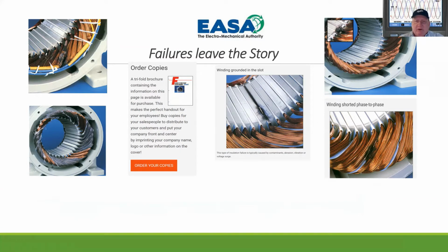So there's also a tool that's out there. Basically, the failures do leave a story. EASA has a product that shows what the motor stators look like when they fail, so you can determine the root cause of the motor failure. This one happened to be a turn failure in one individual phase, so it had a short. This one shows what happens with imbalance. You can see this really charred part here of basically phase A and phase B, but you'll see phase C here of the 4-pole machine has very little heating. So this motor was getting proper voltage on this phase, and these two phases were basically trying to pull the load, and the current would have been higher on those phases than on this one. That's why this one never charred.